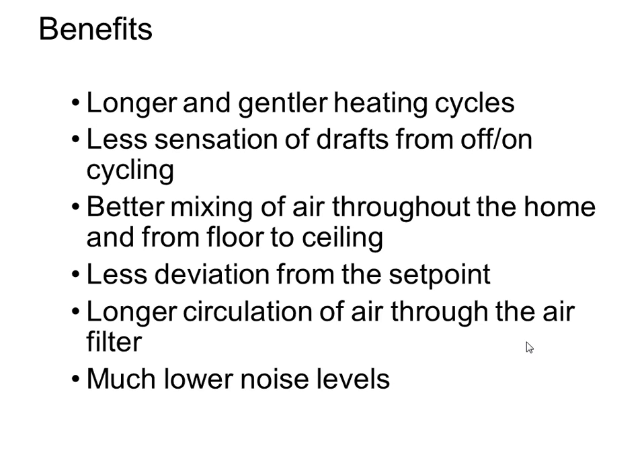The set point accuracy is phenomenal. I have one here in our lab in Melrose Park that we've been playing with for months, and that thing is always within a couple tenths of a degree. Whereas a normal thermostat, usually you wait until it's maybe a degree and a half away from set point, then you turn on your furnace, and then once it gets up to set point, you shut it back off. Then you wait till it gets a degree and a half colder again, then you turn your furnace back on. So you always got at least like a degree or degree and a half of play in there. Well, this guy never shuts off. He just ramps up and down. So it's always like a tenth, 2/10 of a degree from set point. It's very tight control.